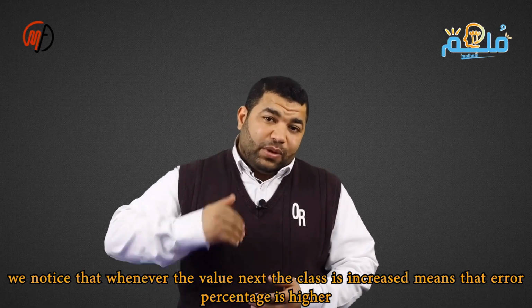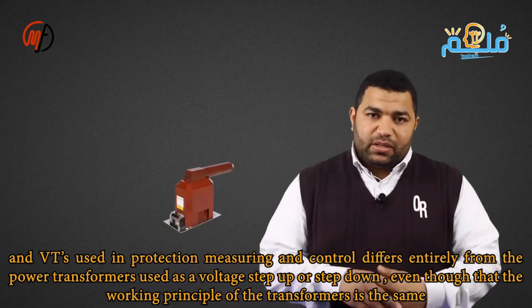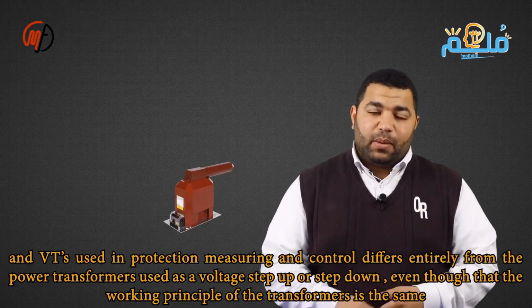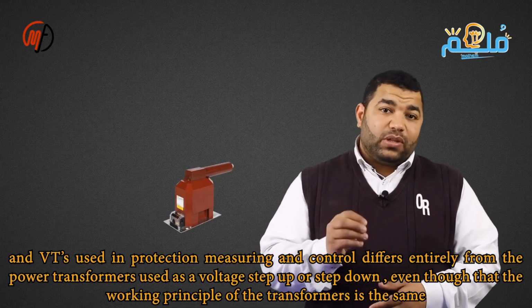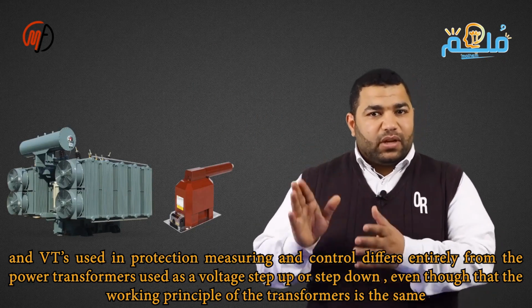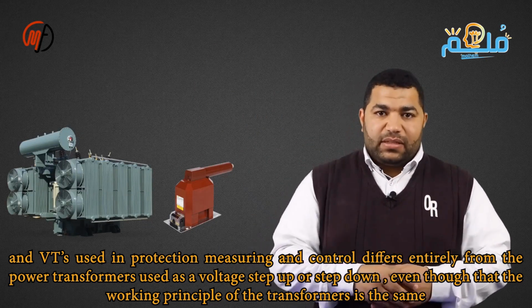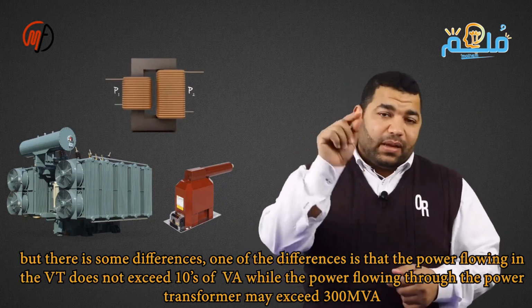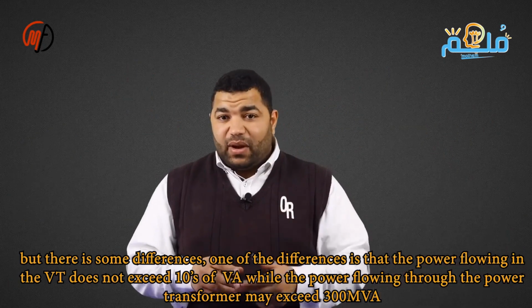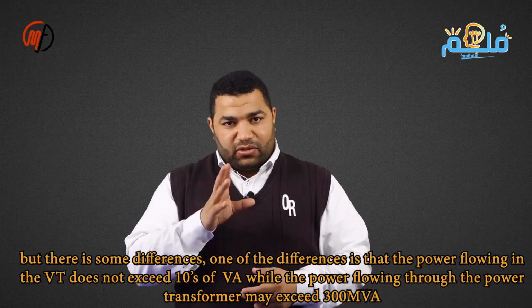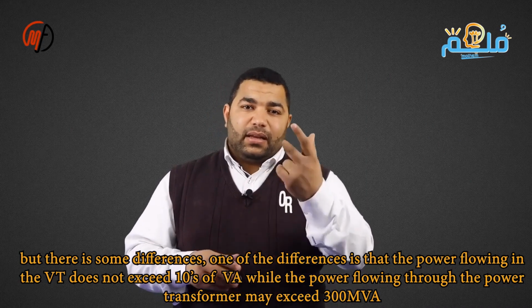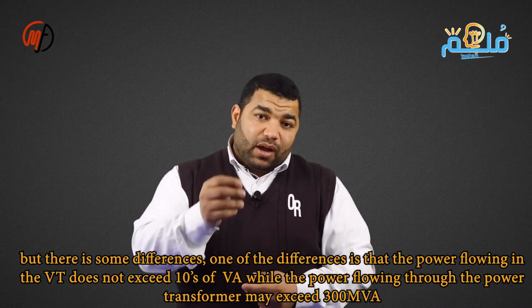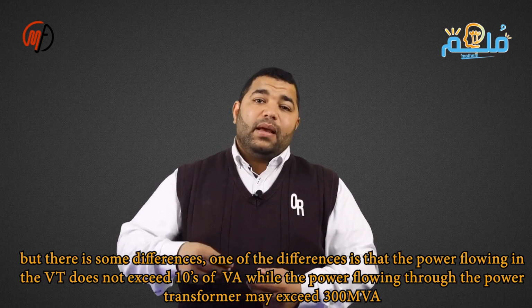Voltage transformers for protection, measurement, and control differ from power transformers used as step-up or step-down voltage. Although both types operate on the same principle, there are differences. One difference is the capacity: the voltage transformer may not exceed tens of volt amperes, while the power transformer can exceed 300 megavolt amperes. Additionally, voltage transformers do not require cooling, whereas power transformers need a complete cooling system due to their high capacity.